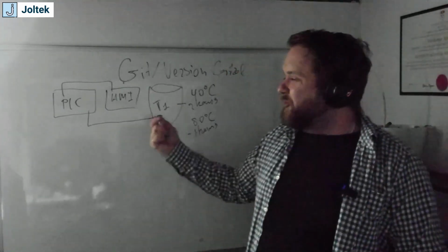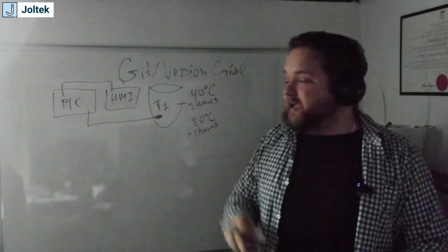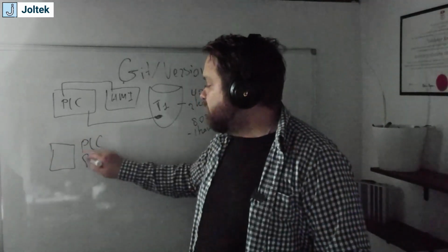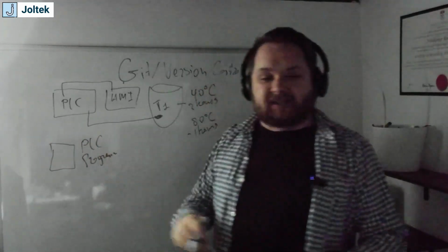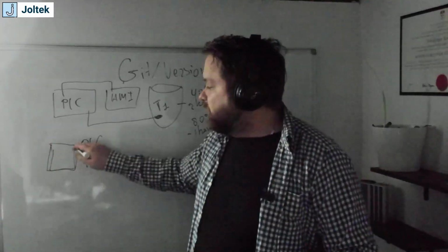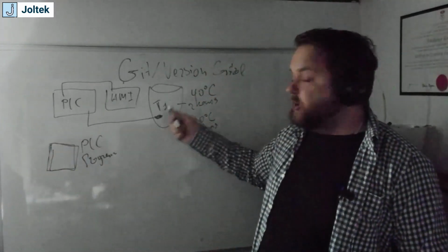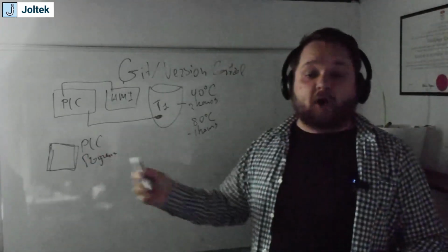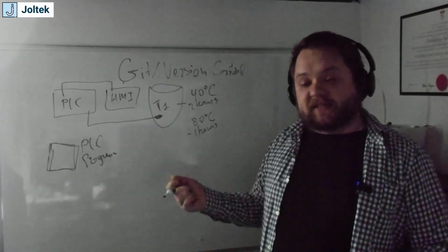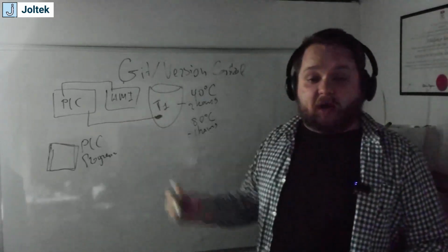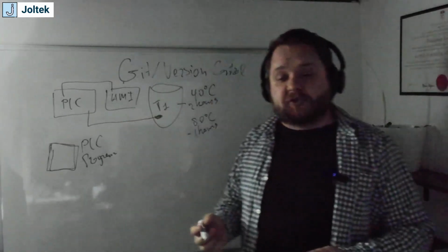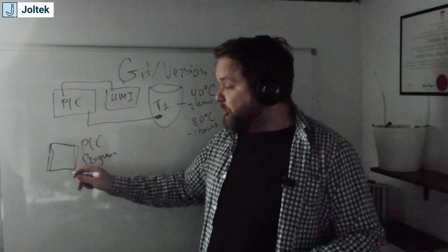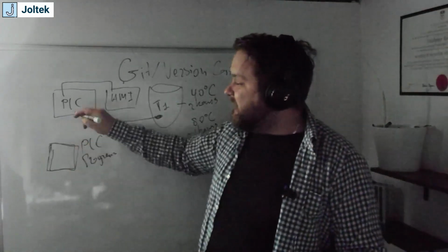So when you're trying to version control a PLC program, this is going to be the file, so PLC program. You do not necessarily just want the PLC program, you also want to be able, not to track necessarily what the register was at every single point in time, but you want to have a certain record of some of those registers as they're being set by the HMIs, operators, or somebody else. Those registers can also be changed by the programmer. So for example, there's going to be hard set values in that program that can be changed and can be pushed to the PLC, right?